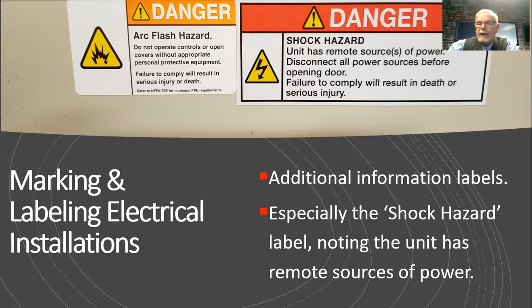So the 70E at an exceptionally extreme minimum is simply a label saying there is an arc flash hazard, and now your qualified staff have to work backwards to find out. Or you can have one of the other labels that identifies the hazard based on the tables or based on a full study.